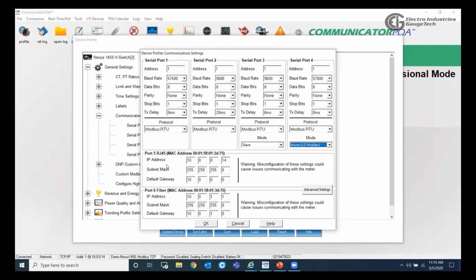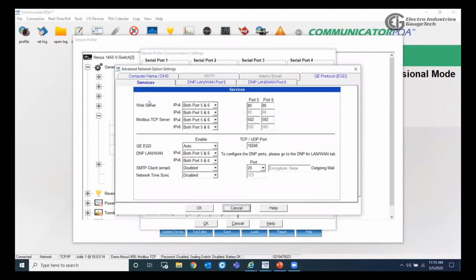On the same page, we also have ports 5 and 6, which are the Ethernet settings. We can set the IP address for port 5 and the subnet mask, and the same for port 6, which is the IP address over the fiber optic. We also have the advanced settings here for these 2 ports. If we hit this one, this is where we can enable and disable the services for ports 5 and 6. As you can see here, the web page is enabled for both port 5 and 6. We can choose one of them only, or we can disable that. We can set the port for each one of them, and the same for the Modbus TCP. We can disable, choose one port, or enable both ports.